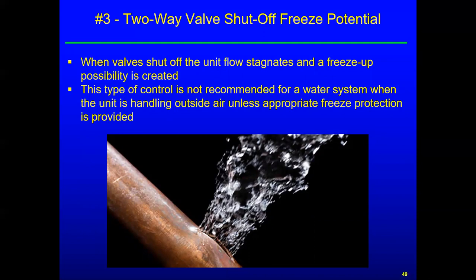So we don't recommend for a water system that the unit be able to completely shut off flow if there's outside air, ventilation air, coming into that unit, because the outside air is the cold source that could potentially freeze the coil. A damper sticks open, because you know this stuff all malfunctions from time to time. And so if you have a stagnant coil and a damper is supposed to shut and it doesn't, bingo, after an hour or two you freeze the coil, it pops, and you've got a big mess on your hands.